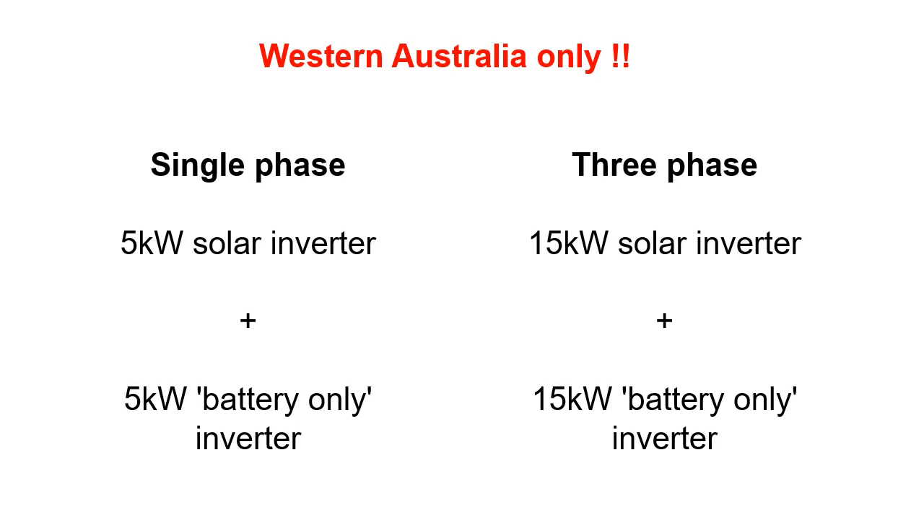Before I move on to DC coupling, I want to explain a Western Australian-specific regulation. If you have single phase, you're allowed a 5 kW solar inverter — which could be solar-only, solar and battery, or a hybrid inverter — and in addition, you're allowed a 5 kW battery-only inverter, such as the one inside a Tesla Powerwall, or the Alpha, Growatt, or GoodWe inverter. If you have three phase, you can install up to 15 kW of solar-only or hybrid, and 15 kW of battery-only inverter. These rules mean that on single phase, you cannot have a 5 kW solar inverter and then a 5 kW hybrid inverter for your battery, which rules out Fronius, Huawei, SunGrow, and other great hybrids as an additional battery-only inverter, because as hybrids they handle battery and solar whether you connect solar panels to them or not.